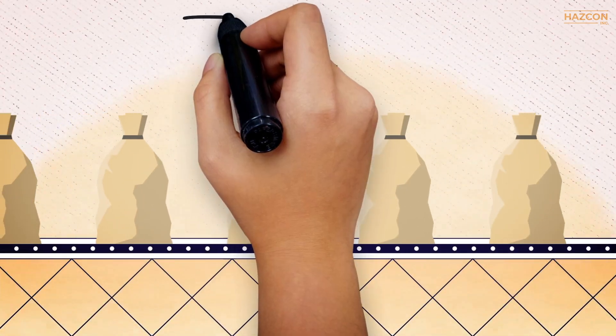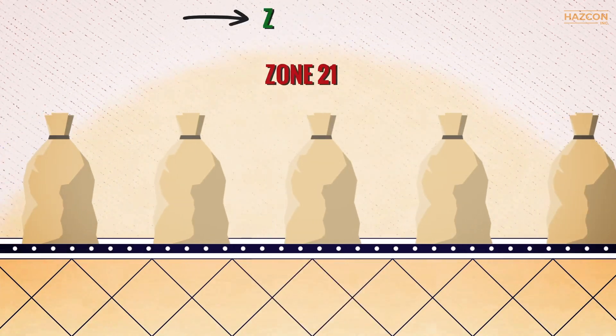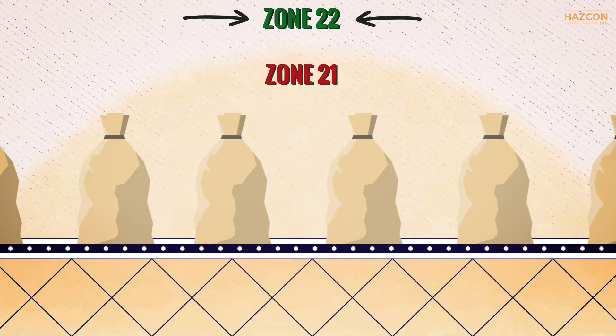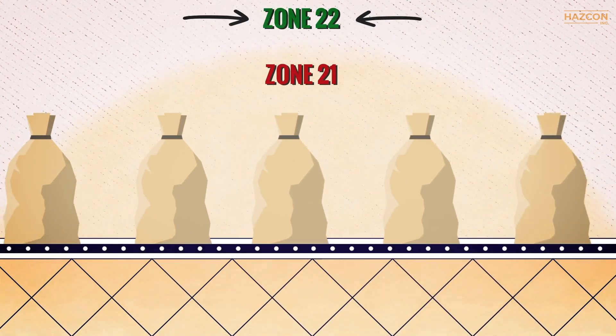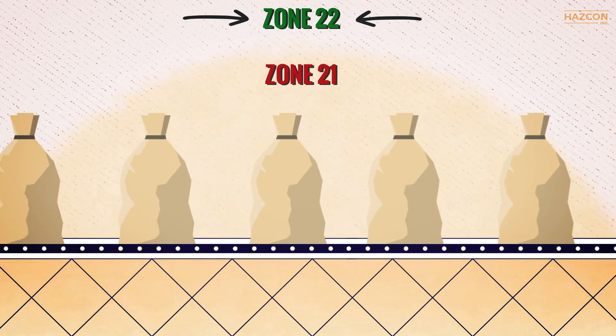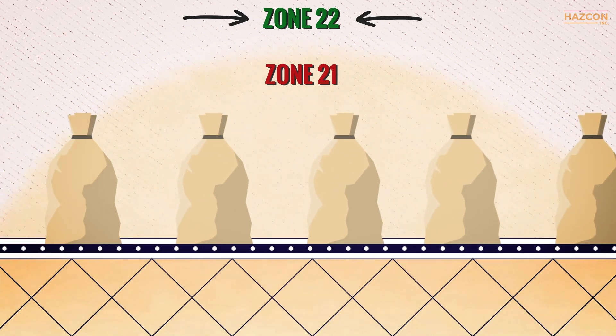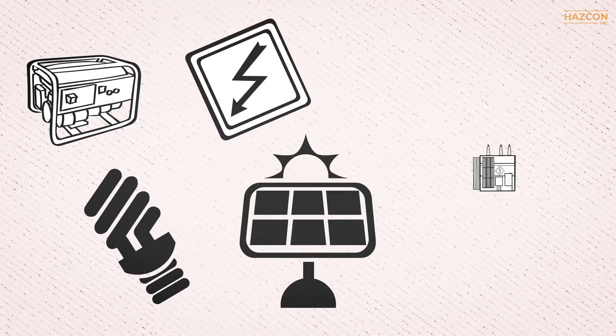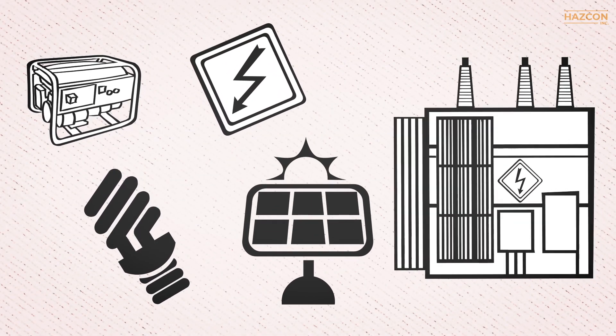This animation is about Zone 22. Zone 22 is defined as an area in which an explosive dust atmosphere, in the form of a cloud of dust in the air, is not likely to occur in normal operation, but if it does occur, will persist for a short period only. Ignition sources must be prevented during normal operation.